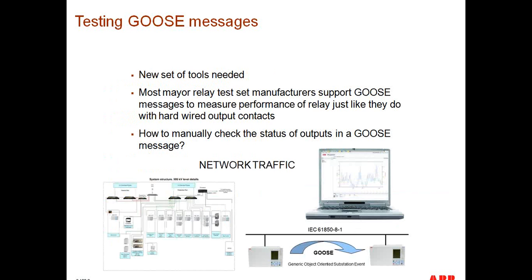Outside this philosophy, we also have to take into consideration that a new set of tools is needed. How do we monitor these GOOSE messages? And the good news is that most major relay test manufacturers support GOOSE messages. Omicron, Megger, Doble, they all offer test sets and software that can monitor these devices and measure that the relays have operated just the same way as they would when an output contact closes and they either monitor potential or continuity.